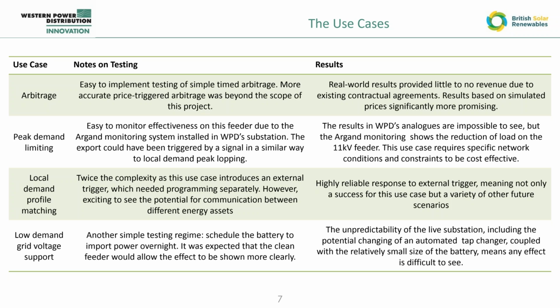Low demand grid voltage support involved increasing loads overnight to help reduce the voltage. So in rural areas where the voltage rises very high on feeders that aren't loaded overnight, we add additional load from the battery, and it was expected this would dovetail with arbitrage and take advantage of lower overnight prices.